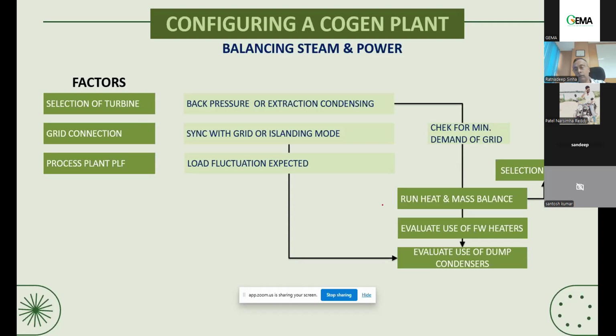Also, there is one check you have to carry out. You all know that when you sign a contract with the grid, the power distribution boards, you have to sign for a minimum demand. How much minimum demand you put is very important, because at the end of the day, if you do not take the minimum demand, you will get penalized. On one hand you are generating power by consuming fuel, coal or biomass; on the other hand, you will have a minimum demand charge. That also has to be taken into consideration when you select a cogeneration plant. And finally, obviously, the final model will come based on your operation cost and the capital cost, of course.